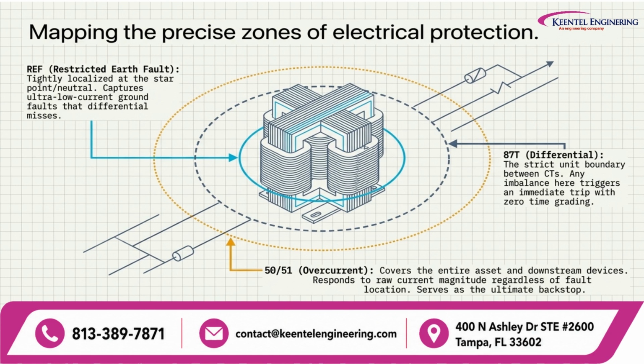Finally, we have overcurrent protection. The 50-51 functions provide a much broader protection envelope. They respond primarily to current magnitude and can provide backup protection for the transformer and downstream equipment. Think of these protection zones as overlapping layers. The closer a protection function is to the fault, the faster and more specifically it can respond. Broader protection functions then provide the necessary backup if primary protection fails.